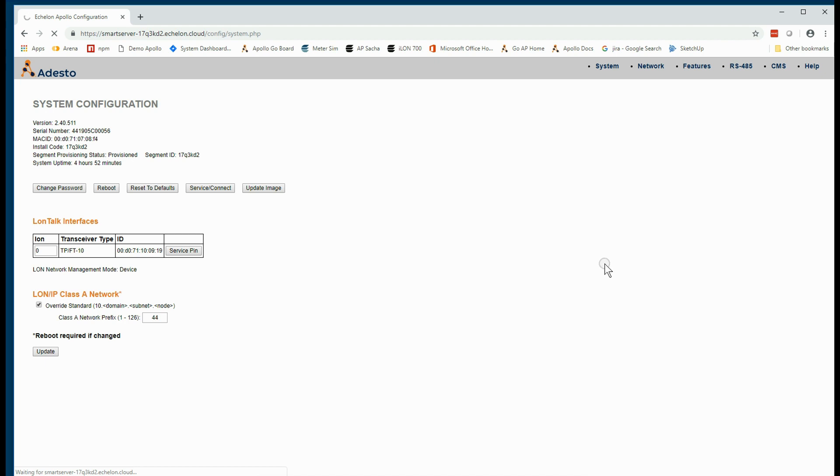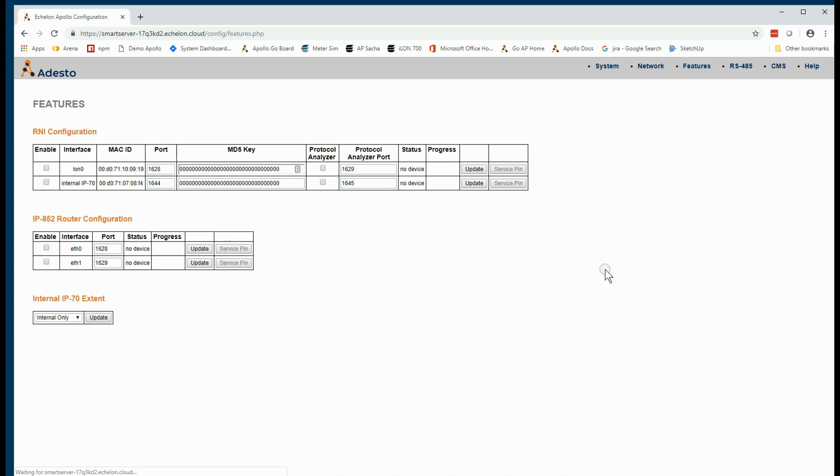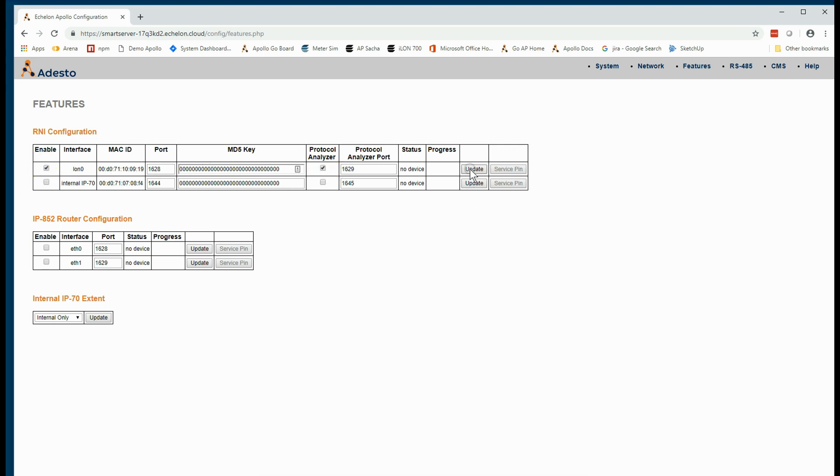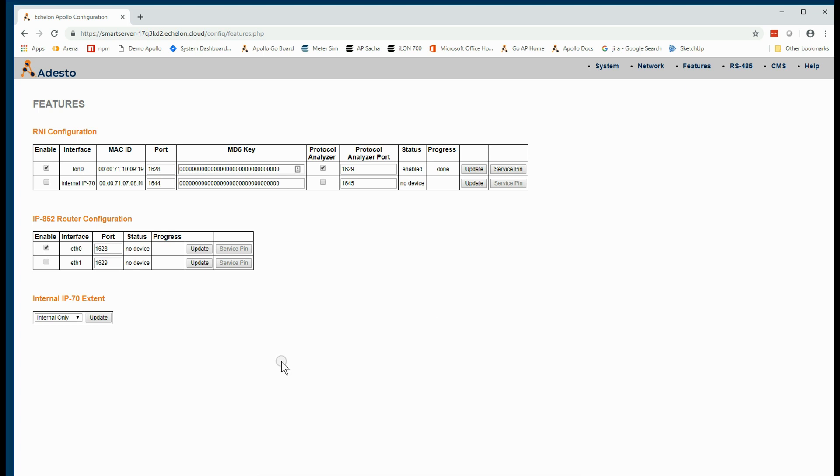In the Features tab, we can enable the different interfaces to use RNI. RNI stands for Remote Network Interface or an interface that is attached by IP. It is important to note that with each feature you enable, you need to lock it in by clicking the corresponding update button. RNI interfaces are ones that are managed with LonWorks32 interfaces in the control panel applet. It's here that we define the ports that are used and whether they're enabled or not.